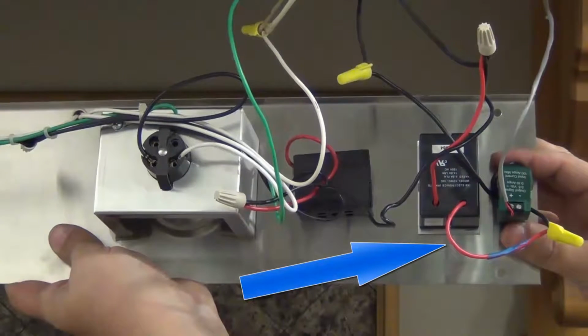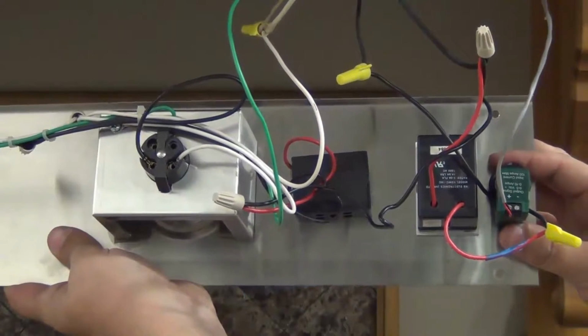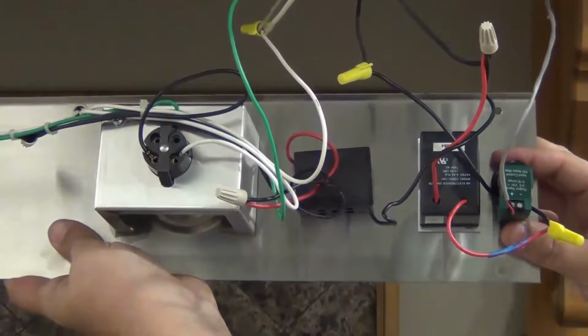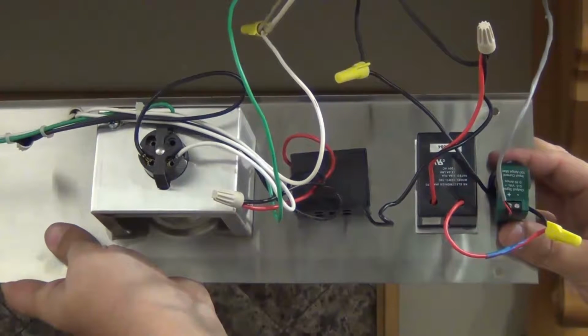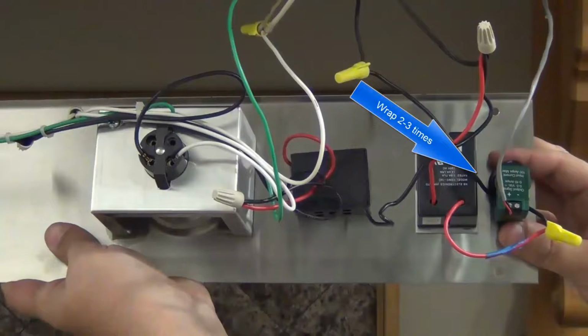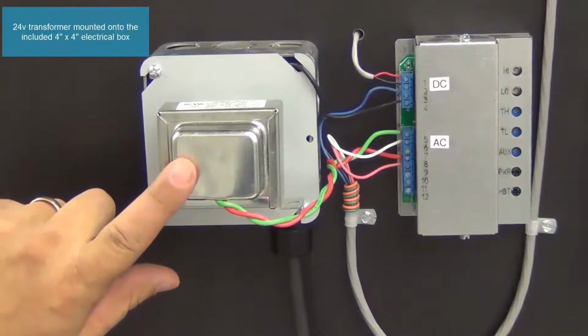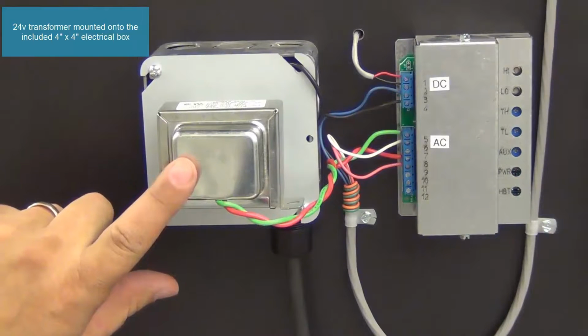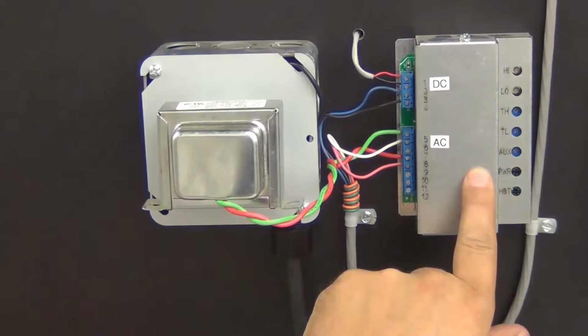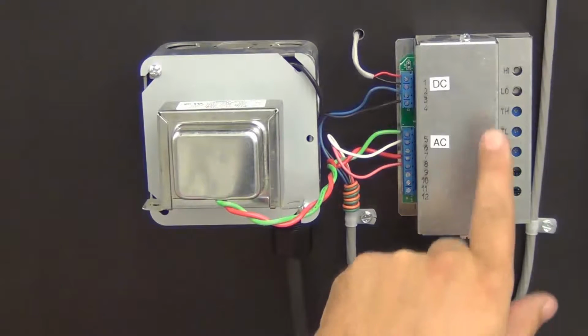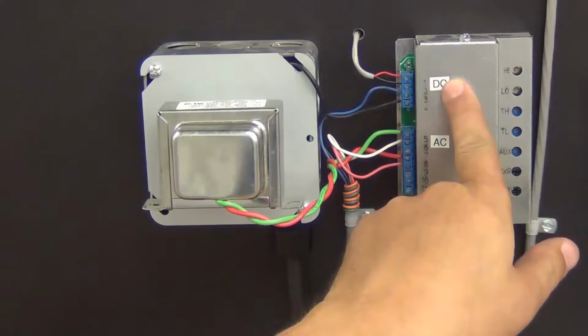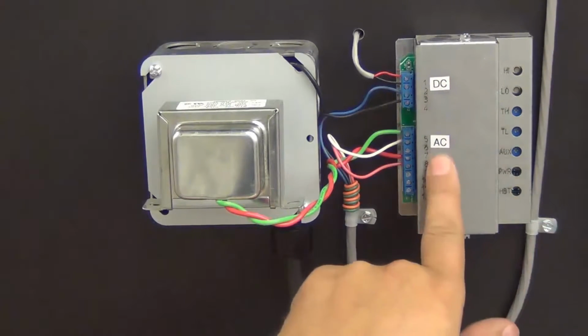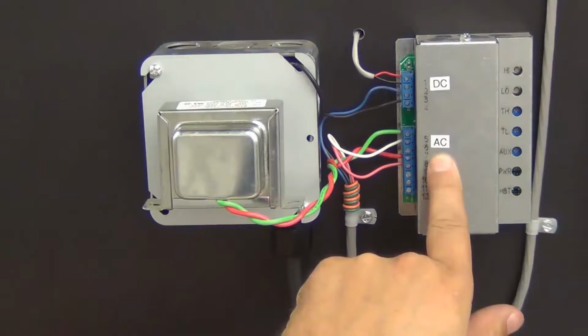However, this transducer can be installed anywhere convenient on the exhaust fan load leg. For applications with load currents less than 1 amp, wrap the fan load leg 2 or 3 times through the sensor aperture so the output will be above 1 amp. The 24 volt transformer has been mounted into the included 4x4 electrical box. The Makeup Air control has all the DC voltage at the top and AC low voltage at the bottom.